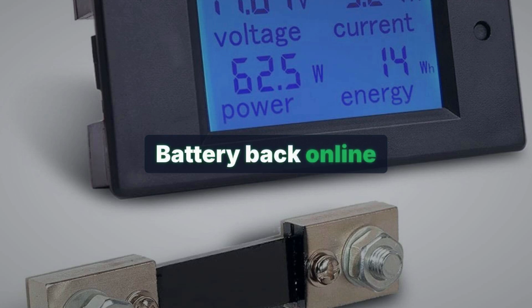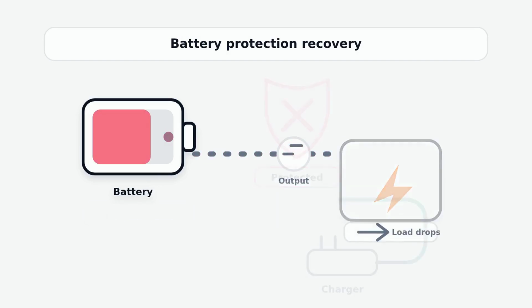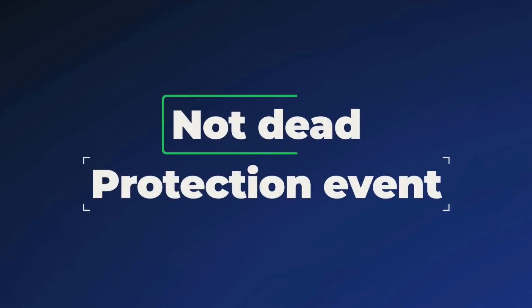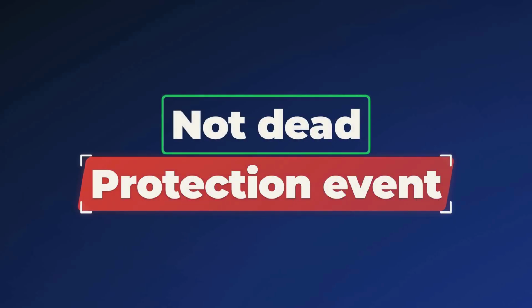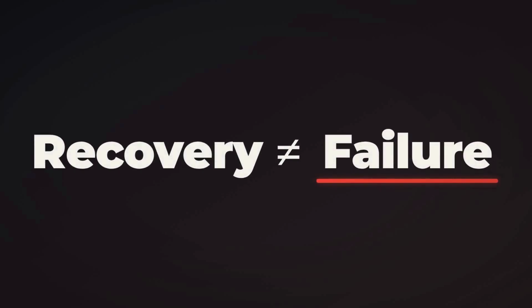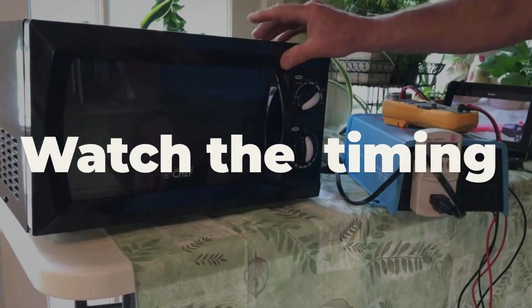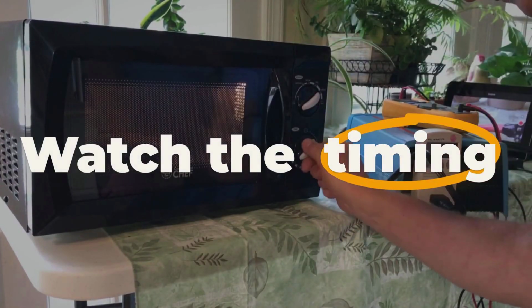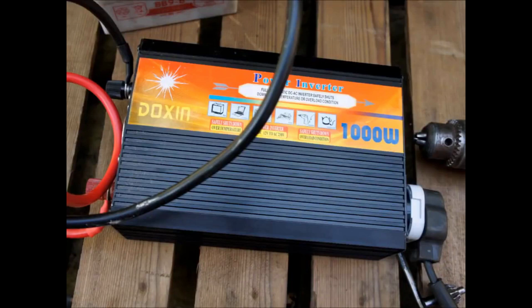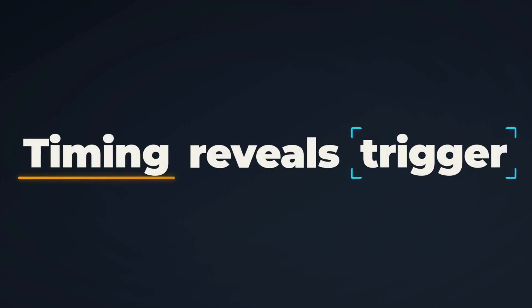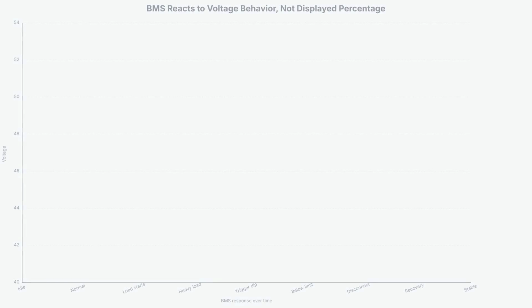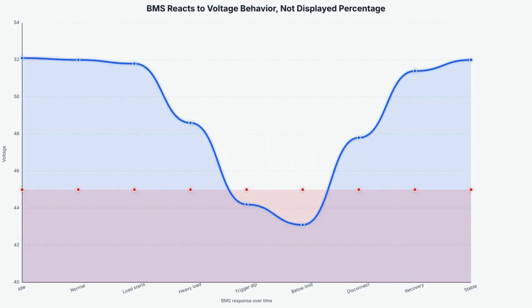But if the battery comes back online after the load drops, or after you plug in a charger, or after the BMS resets itself, that is not a dead cell. That is a protection event. The system cut itself off deliberately and then recovered. Dead batteries do not recover. Now look at when the shutdown happens. If it triggers the moment a microwave runs, or a kettle fires up, or a motor kicks on during a cold morning, the timing is the tell. Those are high current spikes. Voltage collapses briefly under that load, the BMS reads it as a threshold breach, and it disconnects.